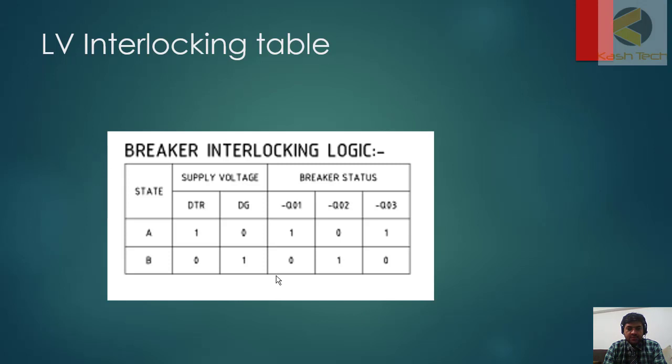DTR is distribution transformer, DG is diesel generator, Q01 is incomer for transformer, Q02 is incomer for generator. In first case, if supply is fed through transformer, transformer is on, generator will remain off, incomer one will remain closed, incomer two which is feeding diesel generator will remain off, and the coupler will remain closed. So all power of substation is fed through transformer.